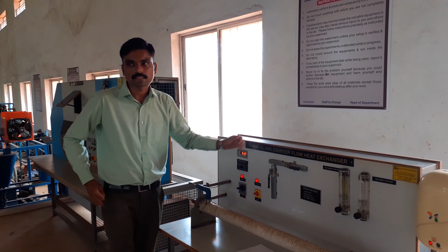The heat transfer for a heat exchanger is given by Q equals U into A into delta T, where delta T is the LMTD value, A is the surface area of the heat exchanger. Don't confuse it with cross-sectional area - it is surface area that you need to consider. The surface area can be calculated using the equation pi d L.